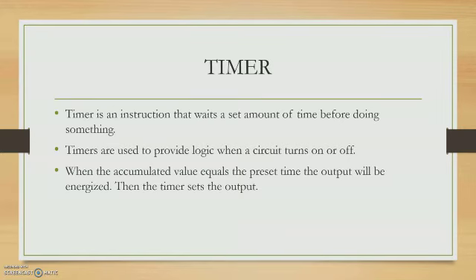The nozzle will operate 3 seconds and at the same time the timer will count for 25 seconds. After 25 seconds the conveyor B will stop to save the power. Timer is an instruction that waits a set amount of time before doing something. Function of timer is used to provide logic when circuit turns on or off. When the accumulated value equals the preset time, the output will be energized.